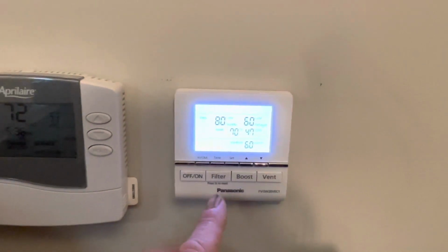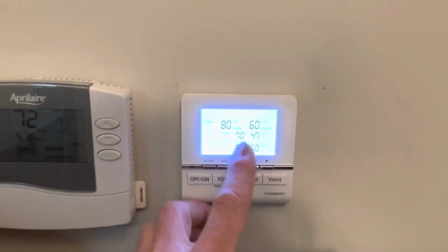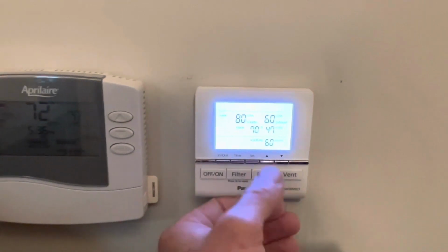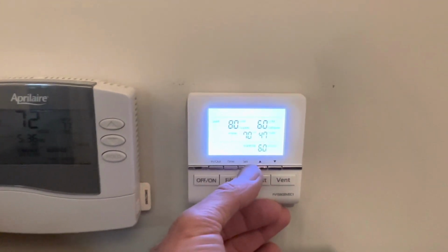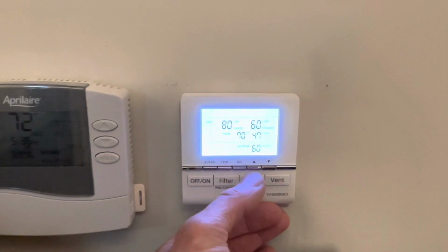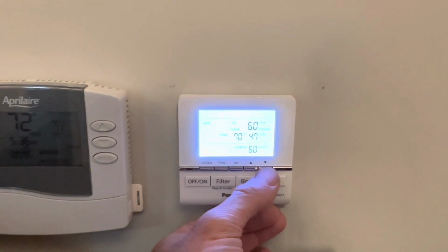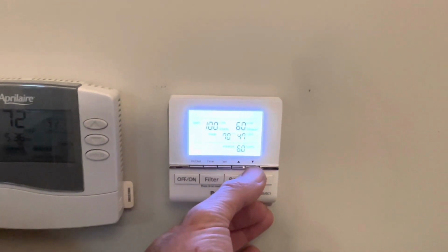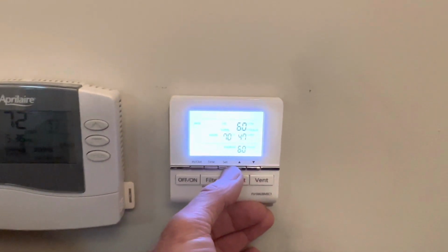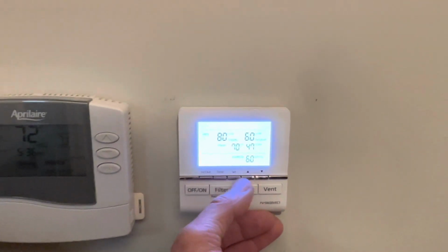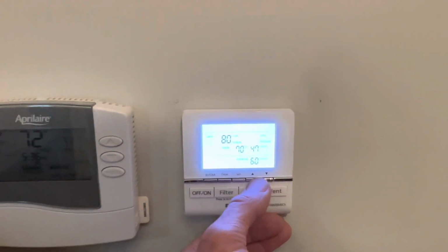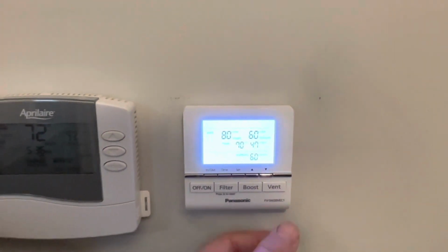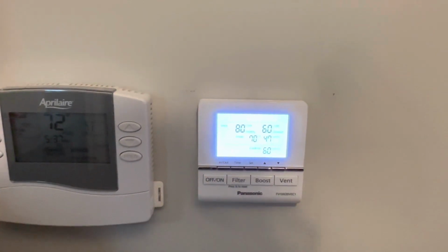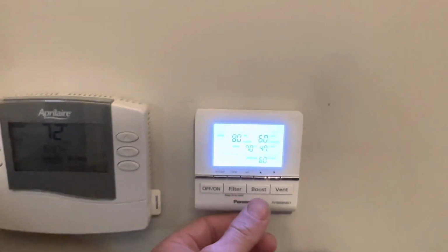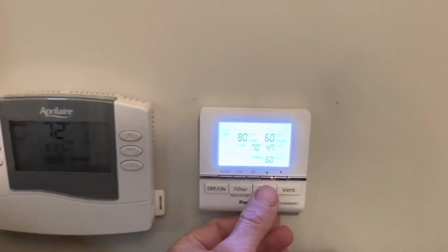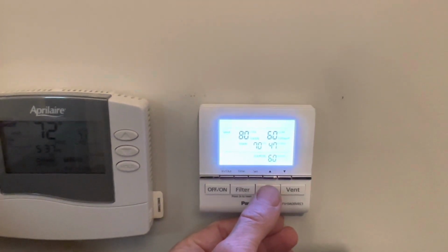Like I said, it's pretty intuitive to set up the CFMs you want. The vent button flashes supply, set. I can raise that up, down. It goes in 20 CFM increments. It's set, switches over to the exhaust. Do the same thing there, go up or down to whatever you want. Hit set, and we're good to go. So I'll push the boost button, we'll go back downstairs and we can see how much power it's using.